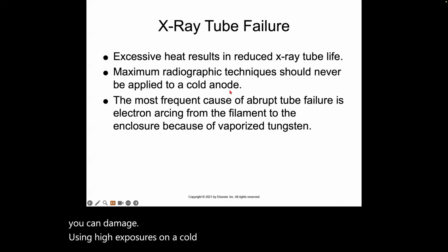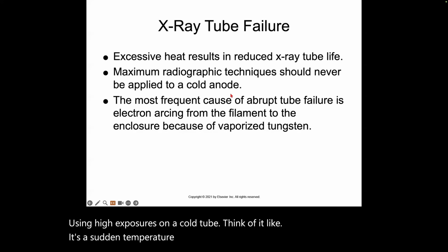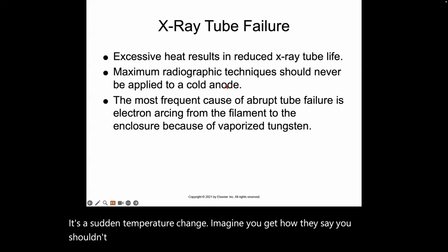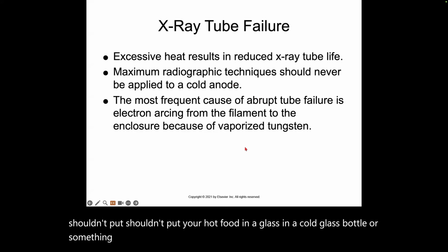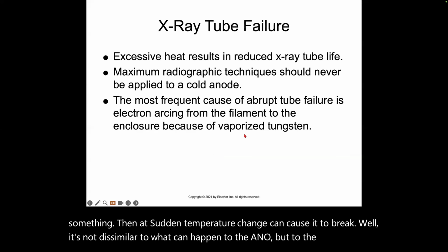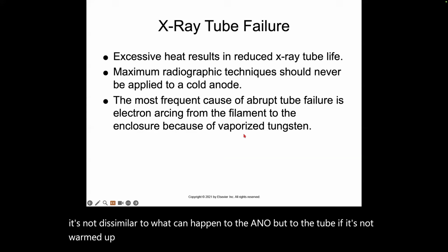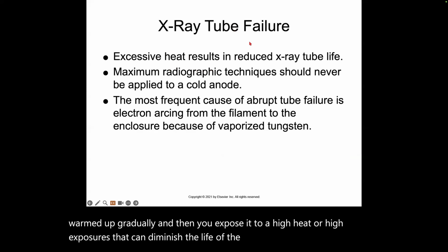Think of it like a sudden temperature change. You know how they say you shouldn't put hot food in a cold glass bottle, because that sudden temperature change can cause it to break. It's not dissimilar to what can happen to the anode or the tube. If it's not warmed up gradually, and you expose it to high heat or high exposures, that can diminish the life of the tube.